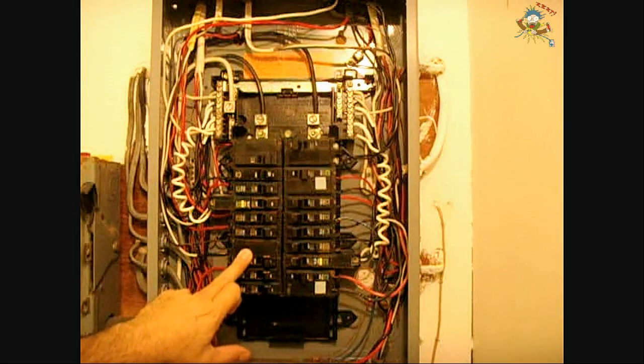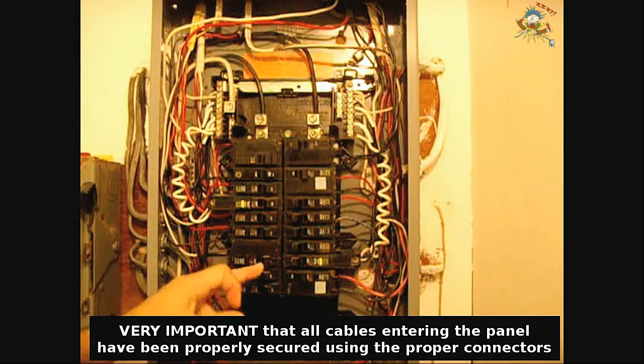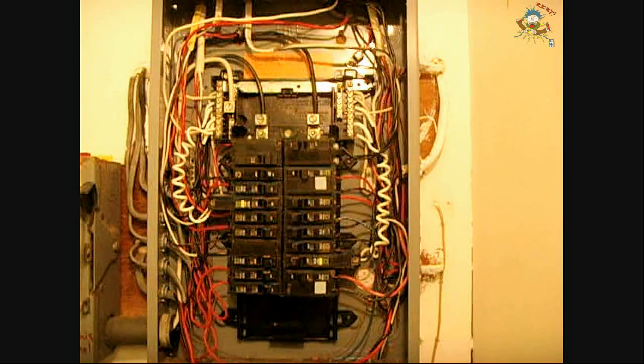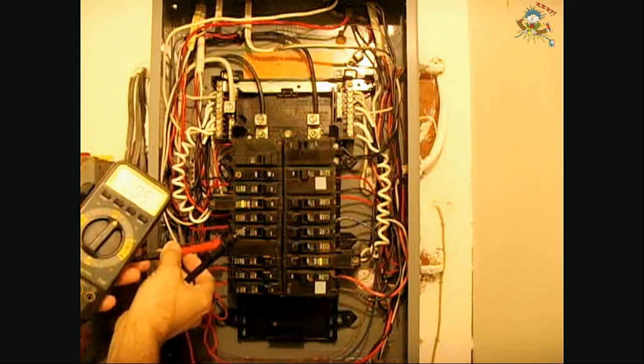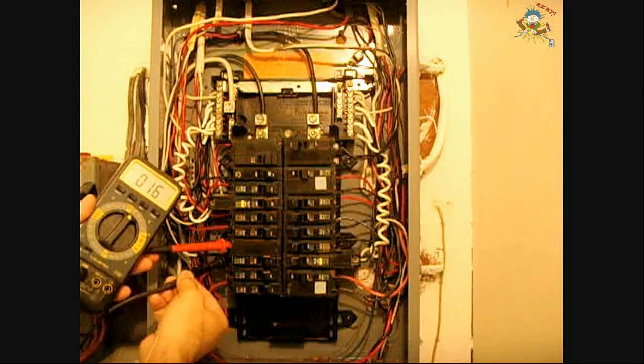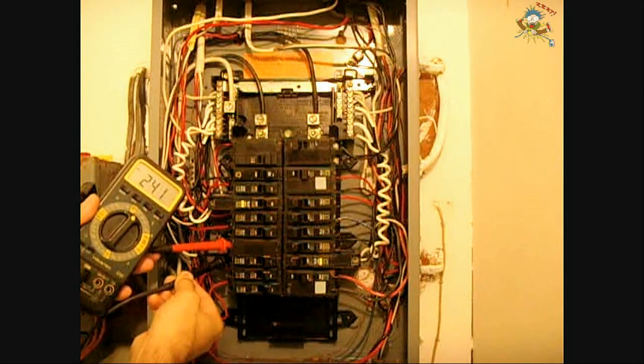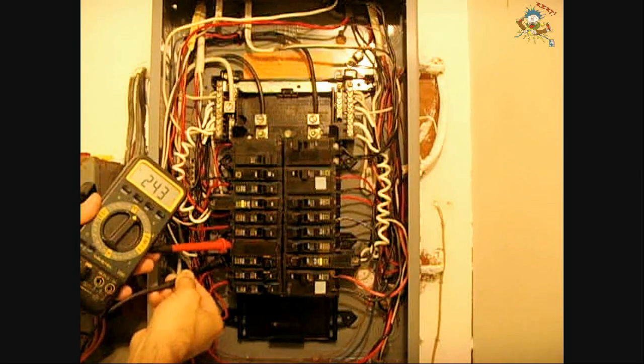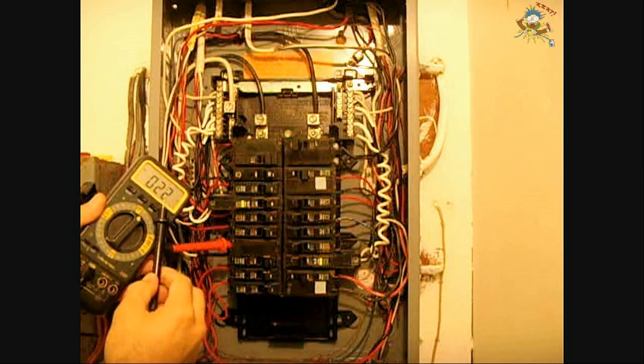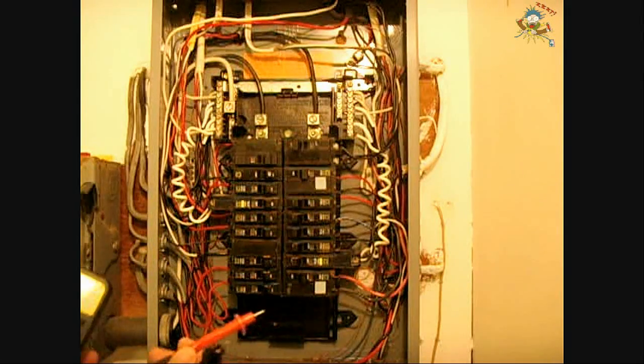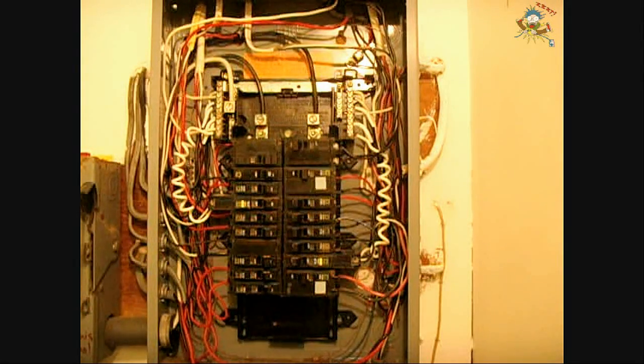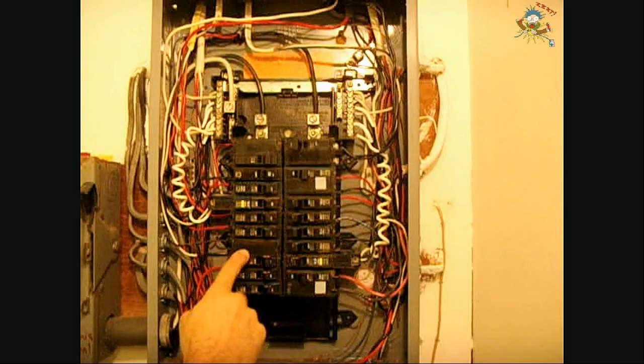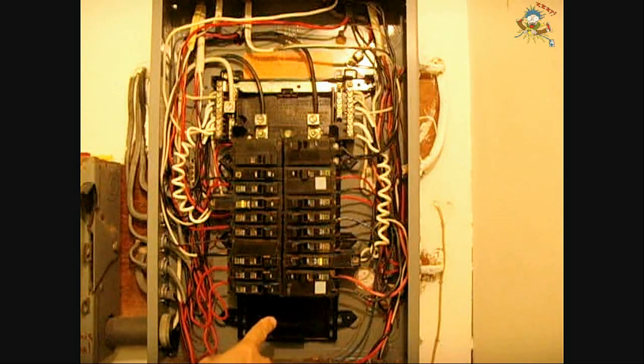If this was a hot water heater circuit, or an air conditioner circuit, or a range, and you think you're having a problem with power at the range, you could leave the two probes connected. One there, and that one there, alright? And while it's connected, you would turn on the load. It's normal to have a little bit of a voltage drop, but if you see that 240 go down to 100 and something, you're going to know there's a problem with either the breaker or the clip where it clips onto your bus bars, and you should check it out.